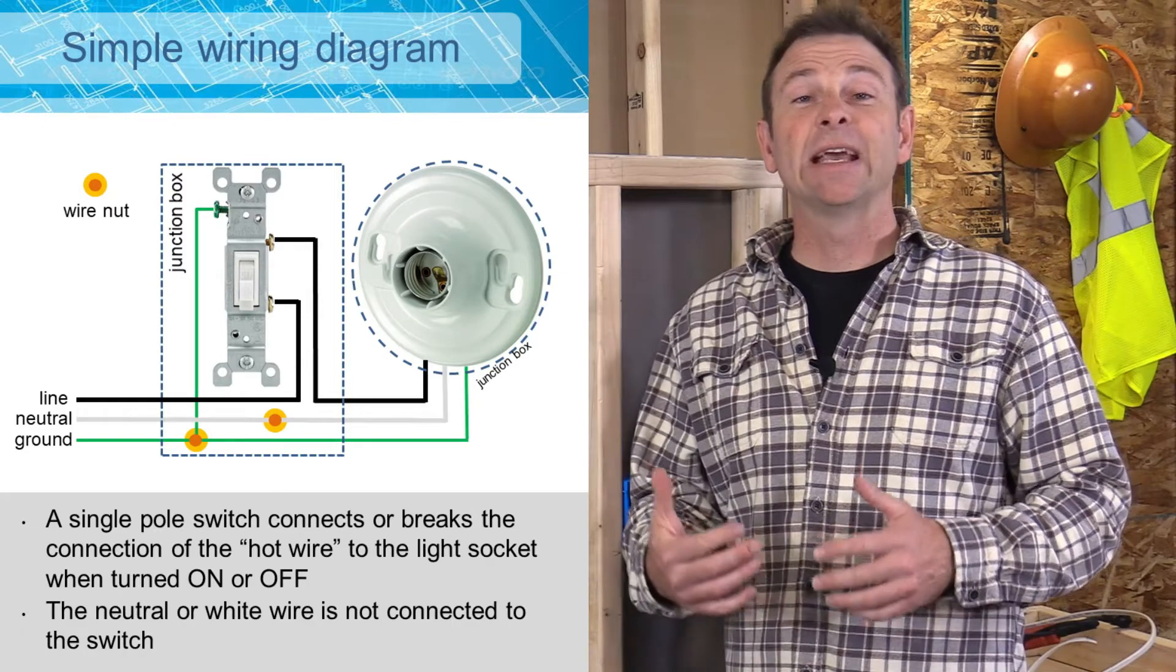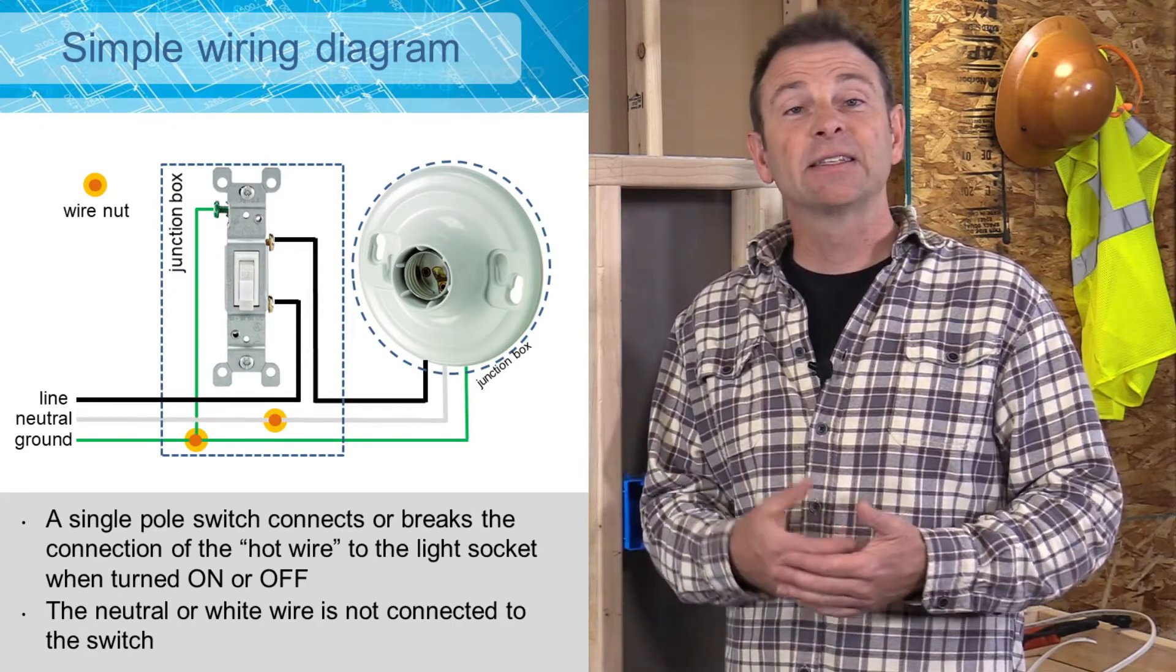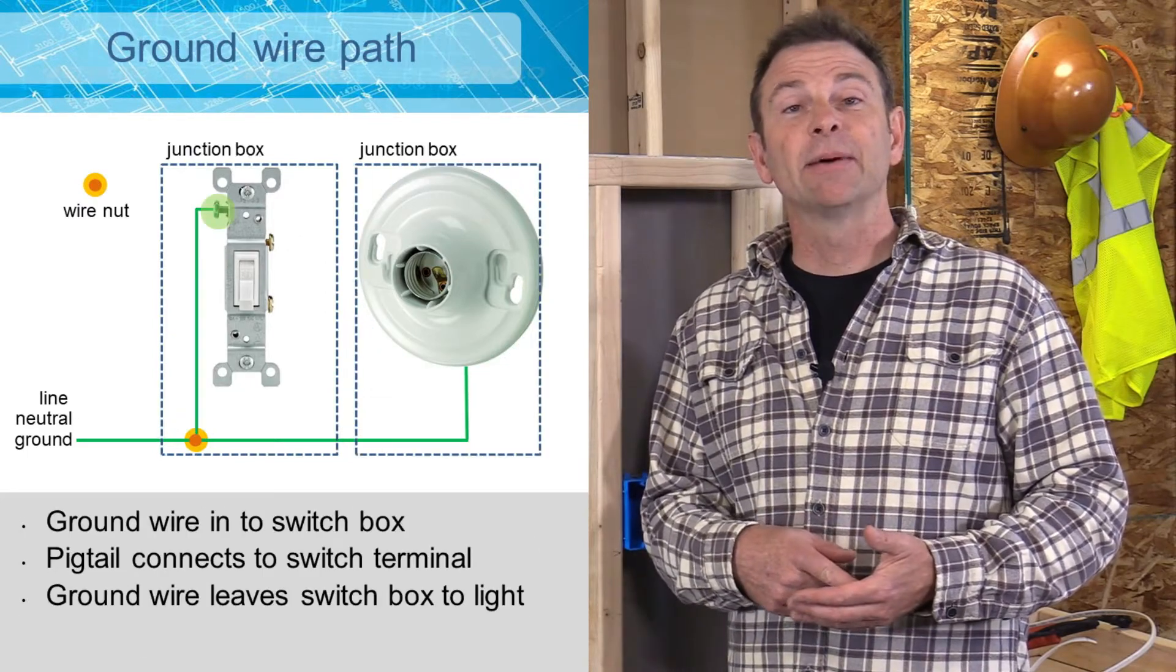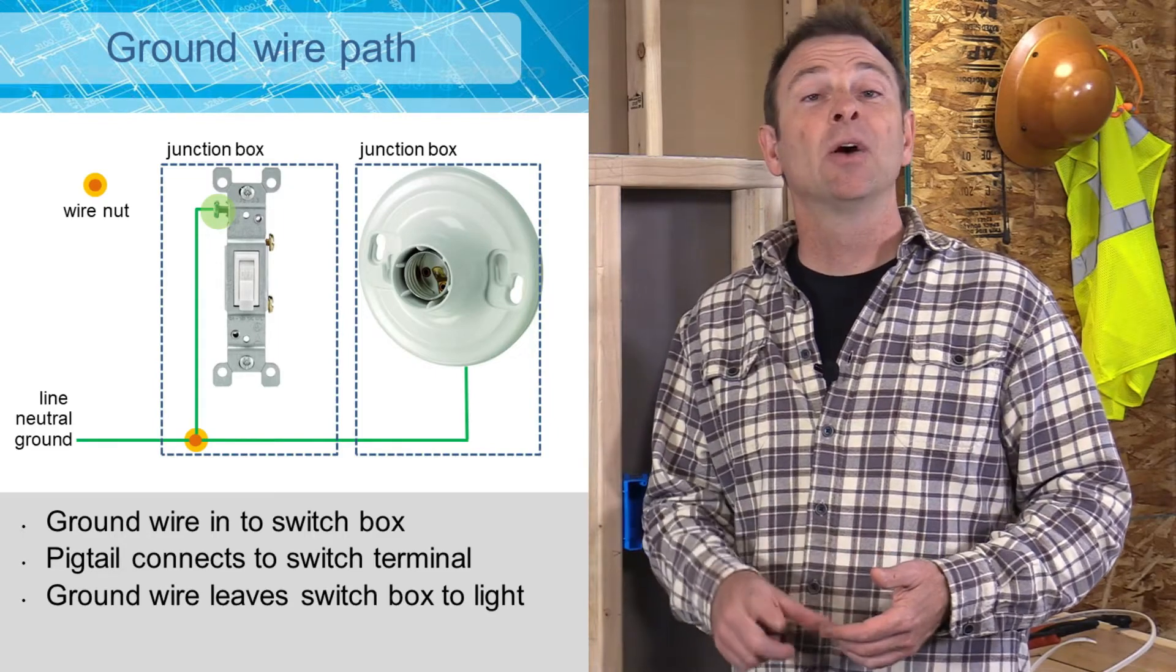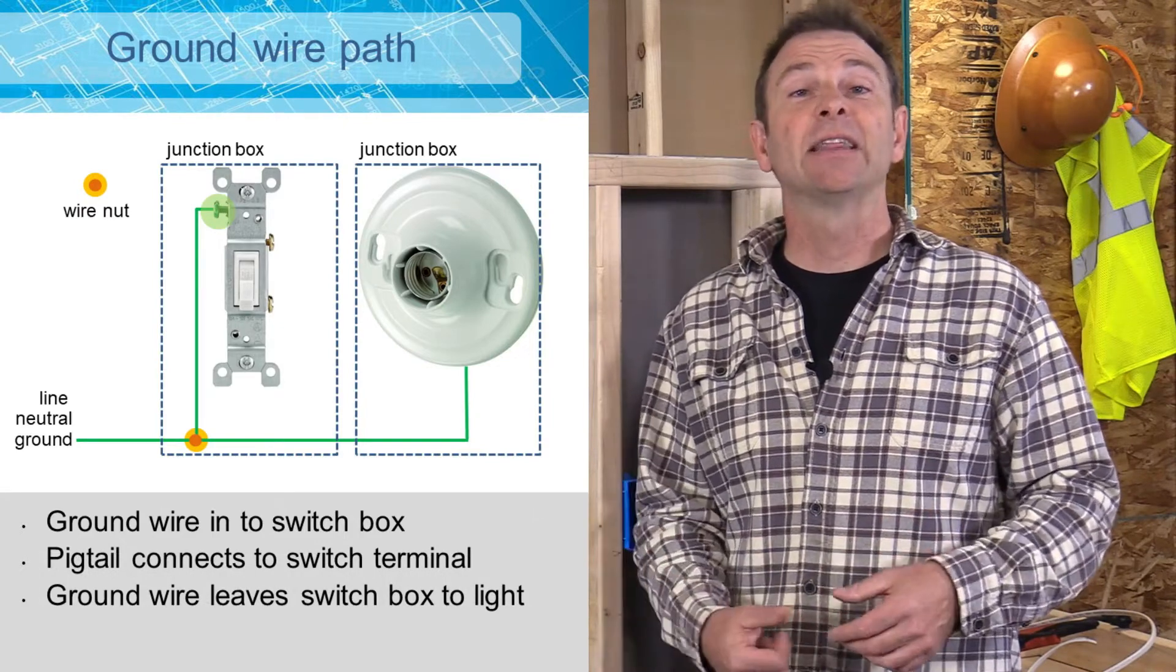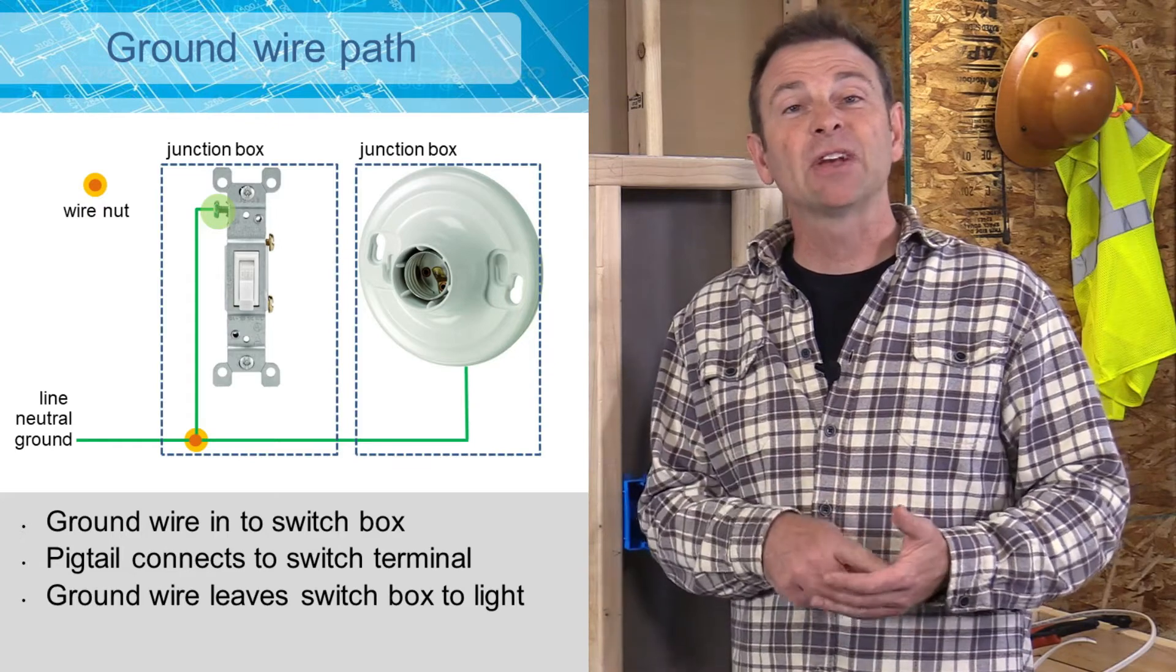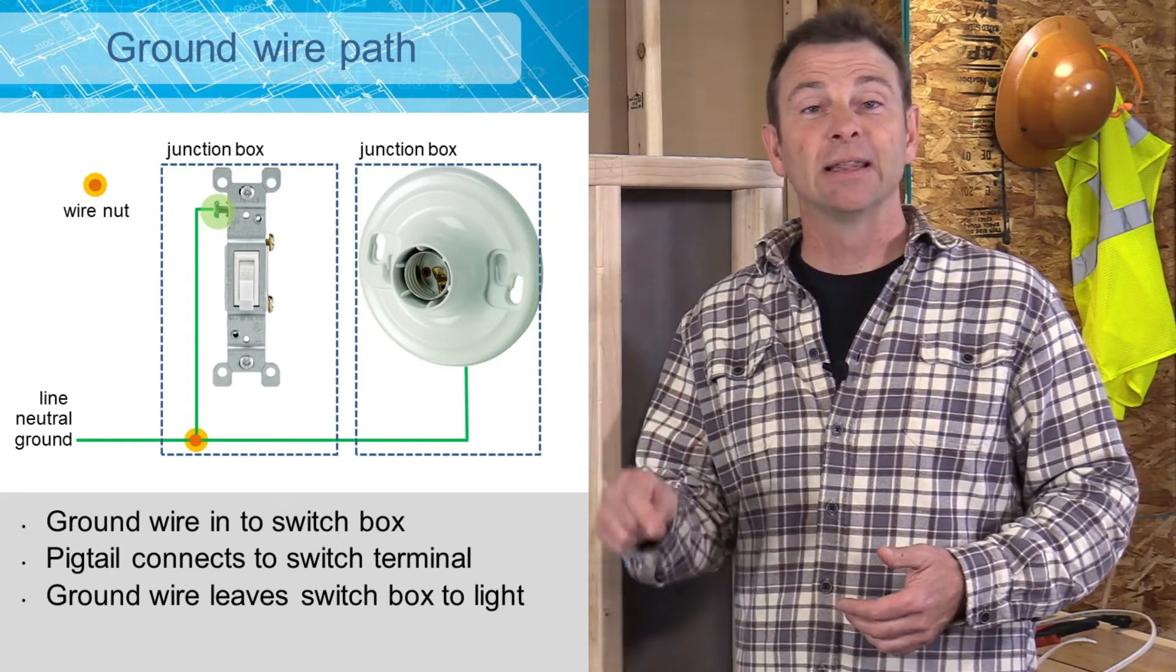Here on the screen you see a schematic of what this circuit would look like. So let's follow these conductors in, starting with our ground. So we have a ground wire that's coming in. You're also going to see a connection to the switch with a pigtail. This is a short piece of wire. If you need more information about your pigtail, check on that lesson that we offer, that mini lesson. The ground is also going to leave out of this box and go straight to our light fixture.